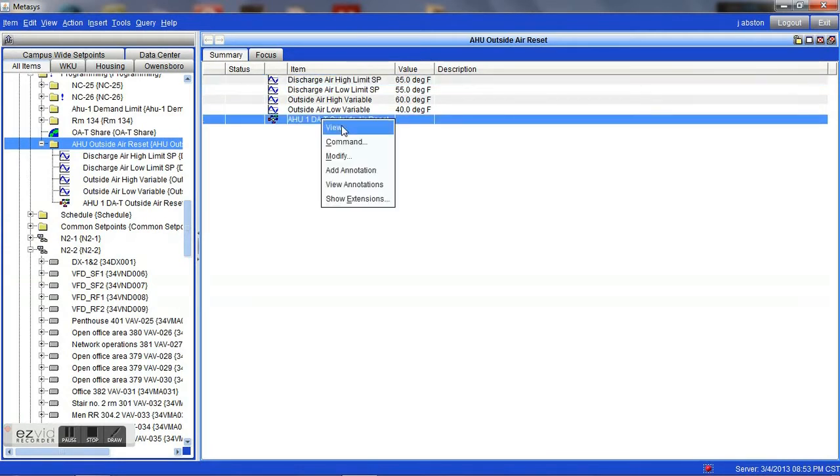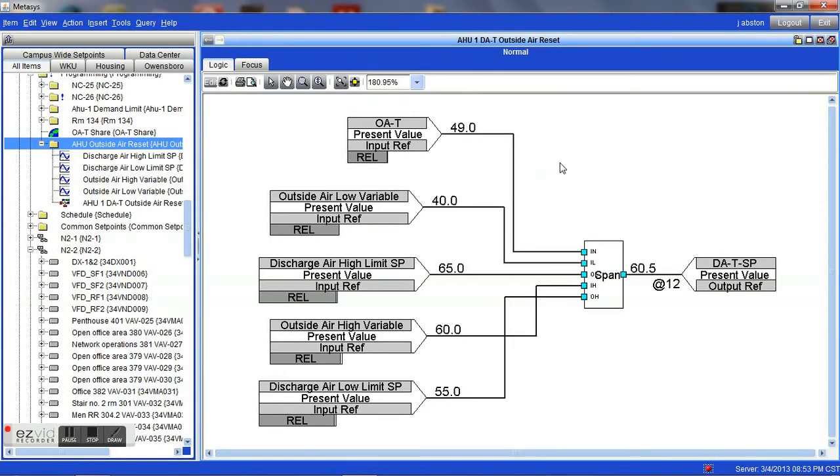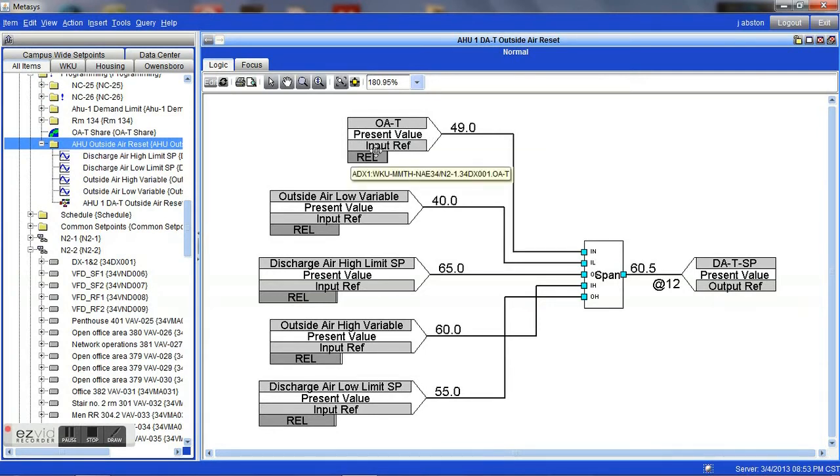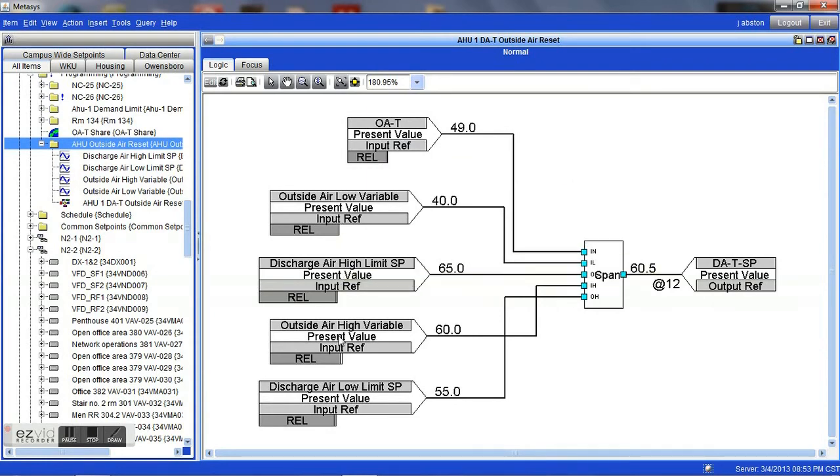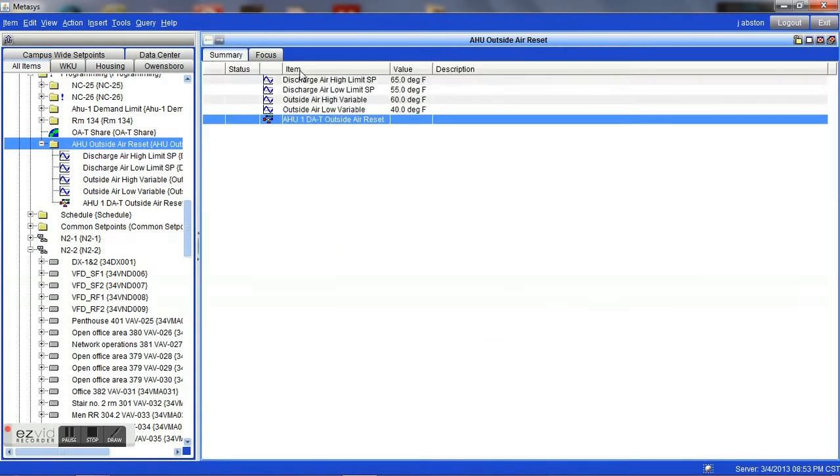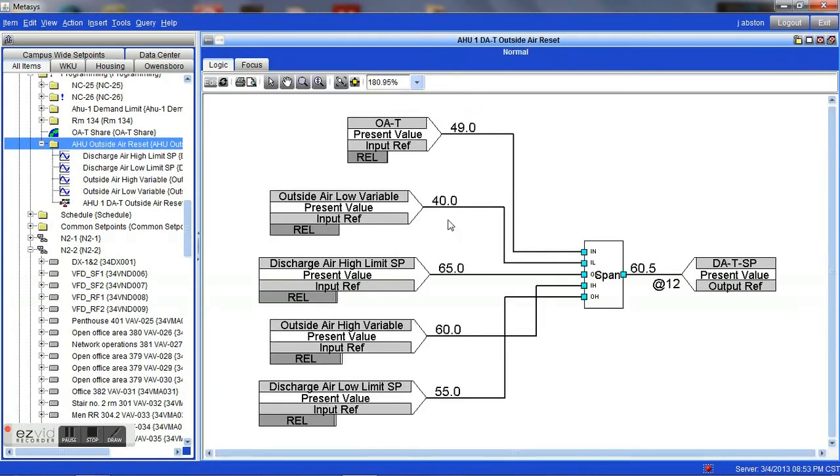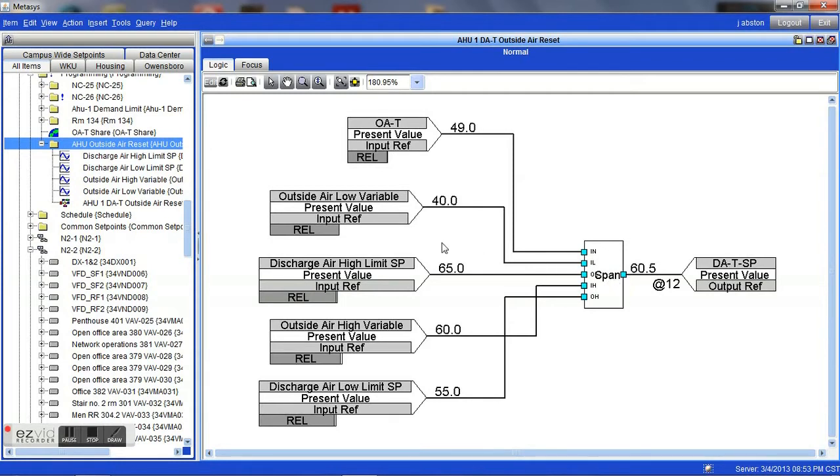It's a very simple logical loop that is created here within the software that can really make your system very effective. As you see here, we have our outside air temperature analog value that's pulled into our logic loop. Here are those points that we were looking at a moment ago, pulled into our logic loop. And they're pulled simply into a span block, which in this case, it just basically performs a simple mathematical calculation, looking at these values and then giving us an output value based upon these.